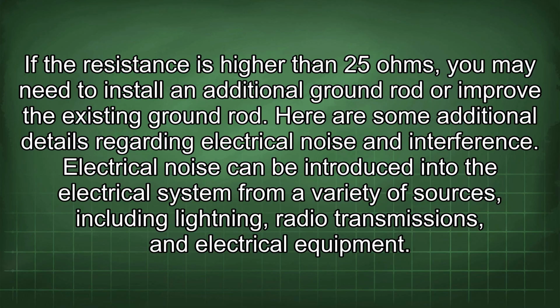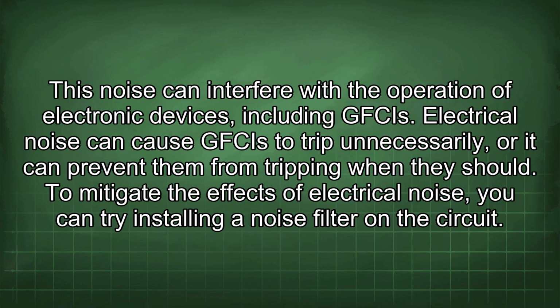existing ground rod. Here are some additional details regarding electrical noise and interference. Electrical noise can be introduced into the electrical system from a variety of sources, including lightning, radio transmissions, and electrical equipment. This noise can interfere with the operation of electronic devices, including GFCIs. Electrical noise can cause GFCIs to trip unnecessarily, or it can prevent them from tripping when they should.